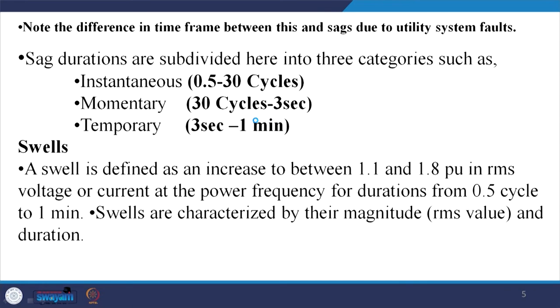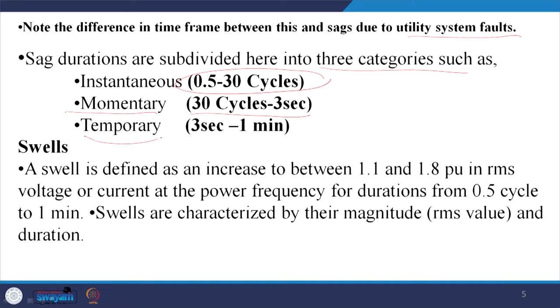Based on the time frame differences between sags due to utility system faults, sag durations are subdivided into three categories: instantaneous sags — 0.5 cycles to 30 cycles; momentary sags — 30 cycles to 3 seconds; and temporary sags — 3 seconds to 1 minute.